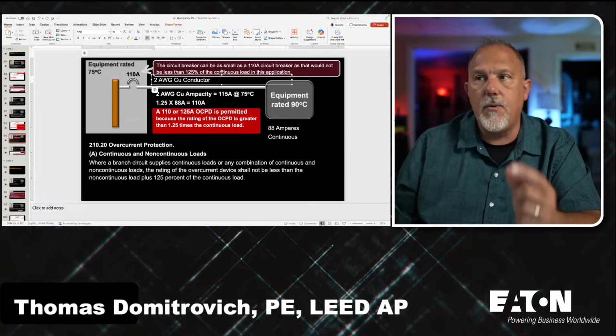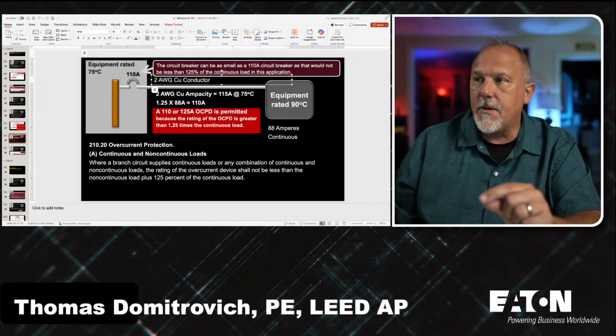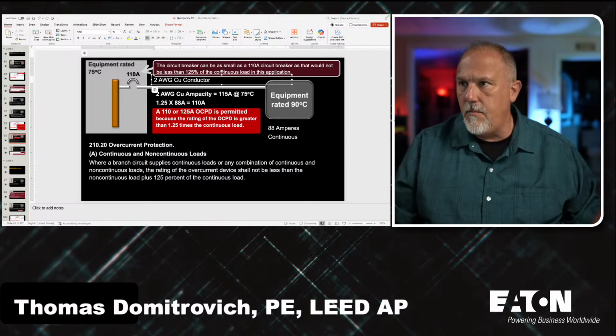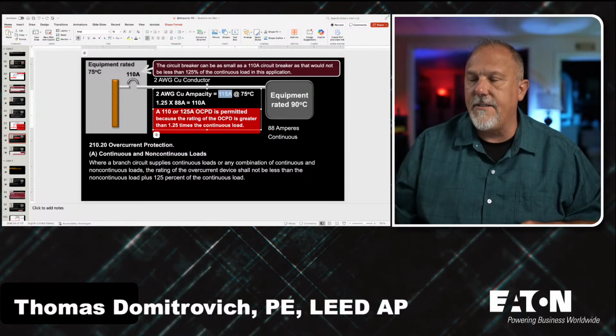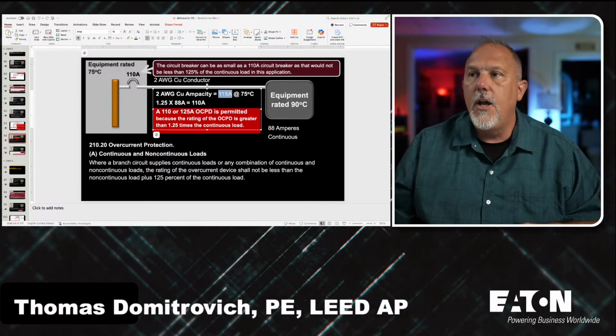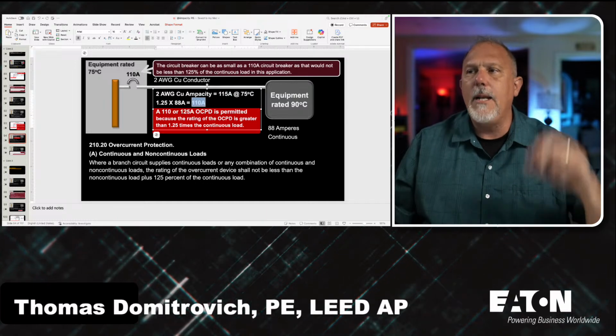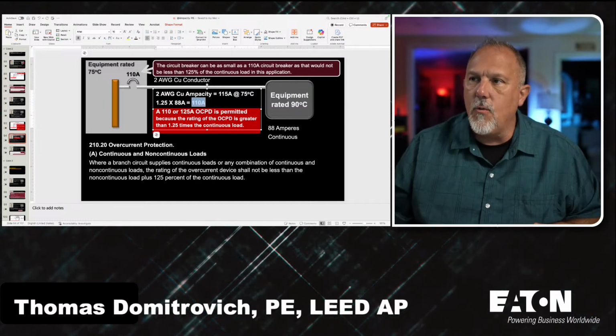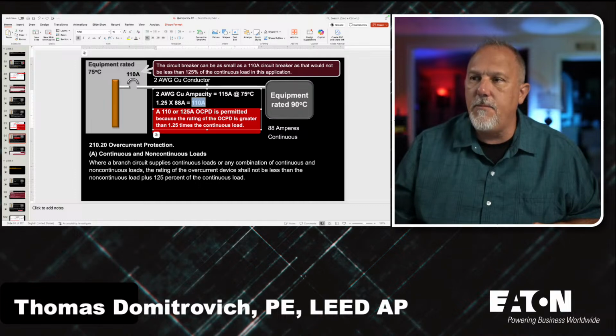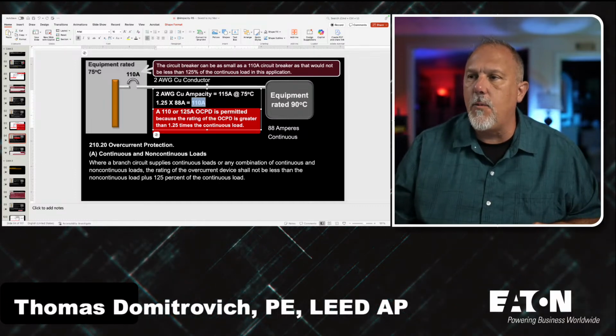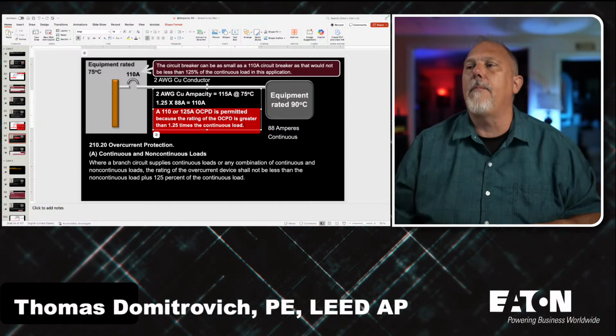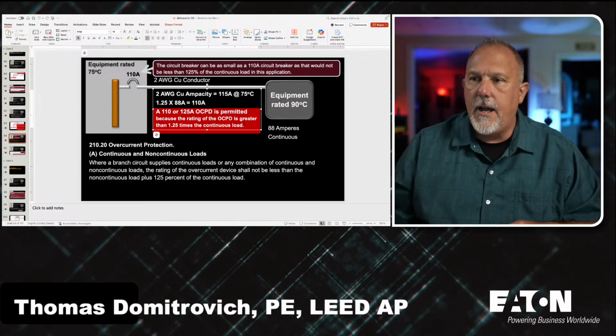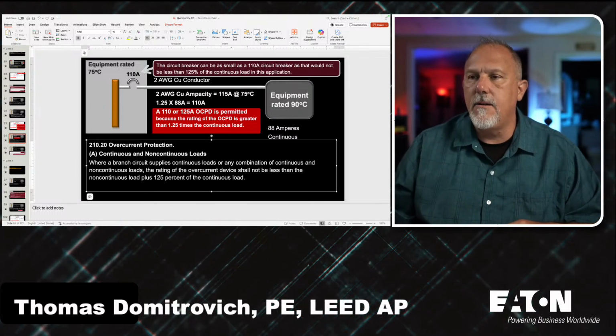What time is it? I got 10 minutes. 2-gauge copper conductor, 115 amps at 75 degrees C. 1.25 times 88 is 110. A 110 or 125 amp circuit breaker is permitted because the rating of the OCPD is greater than 1.25. Perfect. I don't know why I have this here.